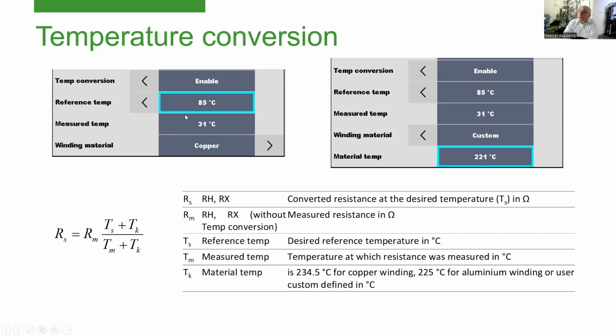Let's say, for example, on the thermometer display I can read that the core temperature is 31 degrees Celsius, and I want the results to be recalculated to the reference temperature, which is usually somewhere around 87, 85, or 75 degrees Celsius. It's up to you, it's not standardized. And with this temperature and this formula, the final value which you see on the screen is calculated. So the instrument does that calculation, and you only have to define for such a measurement which material was used, the actual temperature, and the reference temperature. You can also enter special materials if you have them; you need to know the material temperature data about that winding.